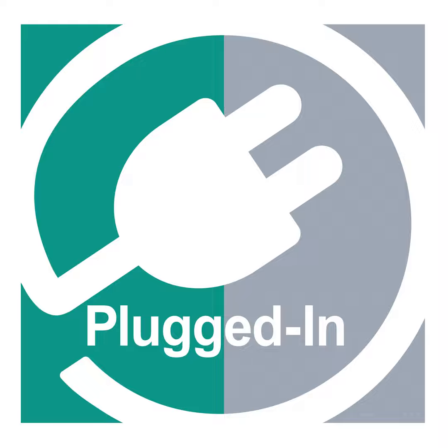And what specifically makes an outdoor cable? Right. Well, it has very good resistance to the environment you'd find outside. UV protection, seawater protection. UV means sun. The sun, that's right. Yeah, ultraviolet rays. Seawater, oil resistance, diesel fuel resistance, and the PUR-O, outdoor rated cable, has the biggest temperature range from negative 50 degrees Celsius to 105 degrees Celsius.